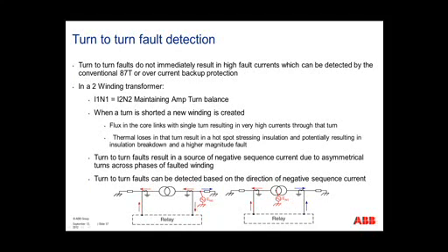What is the trip time of differential relays in cycles? It's going to be sub-cycle. That's going to be vendor specific. However, you're looking at less than a cycle.